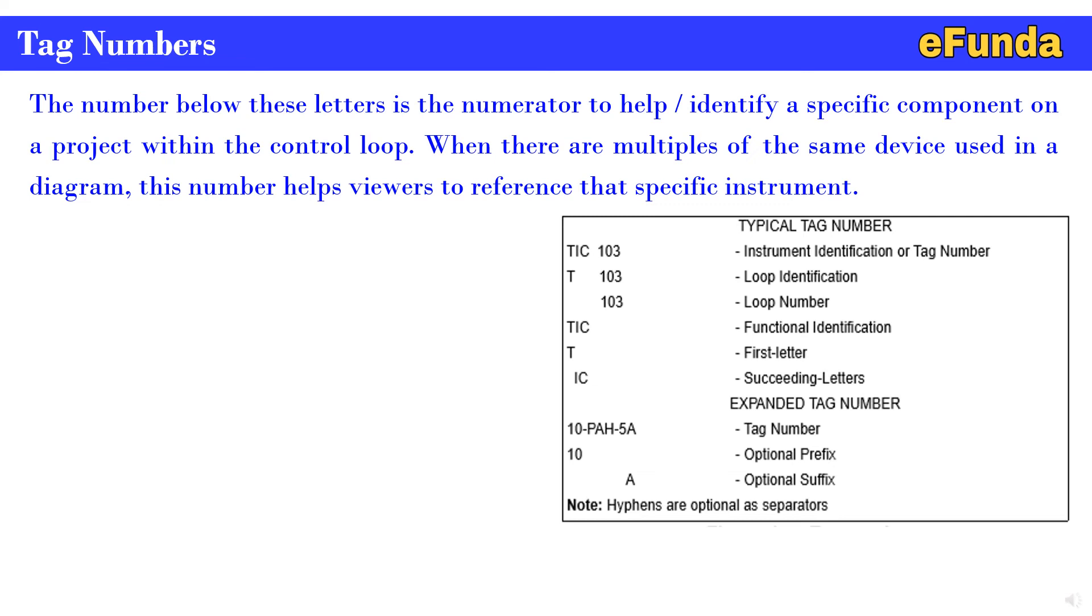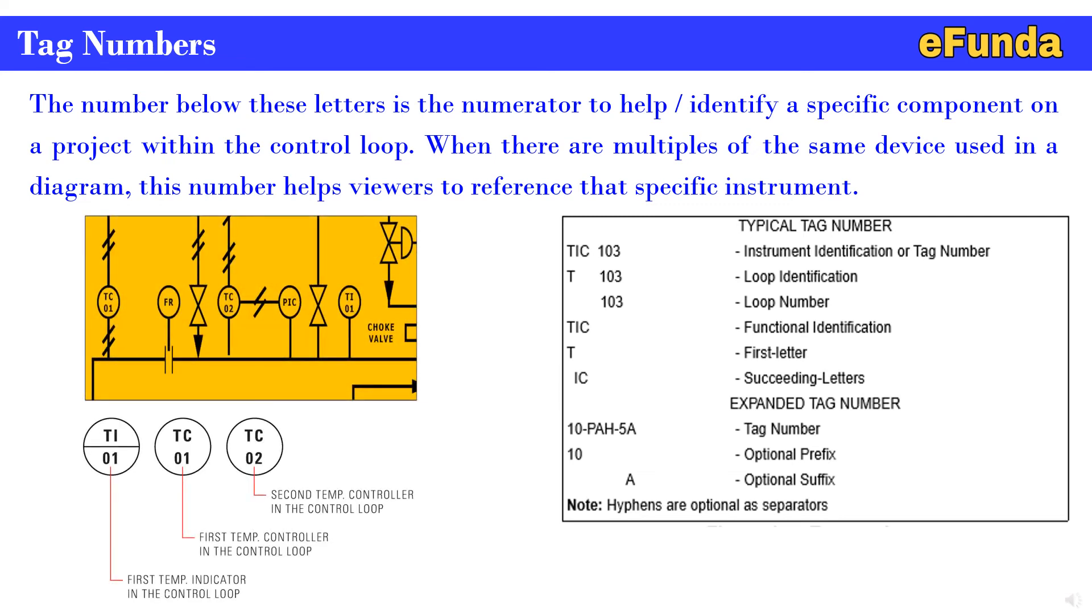Similarly, on the left hand side, one can see the P&ID diagram where TI, TC, TC are indicated. We will see the details here. TI-01 is the first temperature indicator in the control loop. TC-01 is the first temperature controller in the control loop. TC-02 is the second temperature controller in the control loop. This is how the tag numbers are used for identification of the multiple functions or multiple devices used in the diagram.